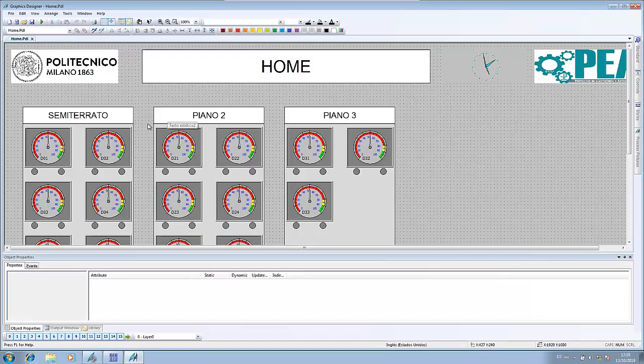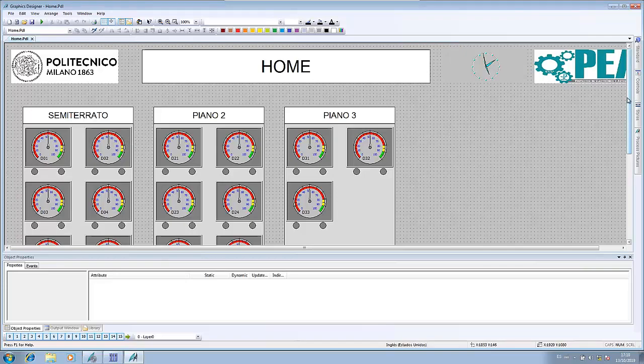The other principal editor is the graphic designer. In graphic designer, you can create different PDLs which are the names for the screens, and I will open the home or the main screen of my thesis. On the graphic designer, you will be able to add graphical objects which can be static or dynamic. In case of being dynamic, you can make this dynamic of the object be attached to a variable already created in the graphic designer.